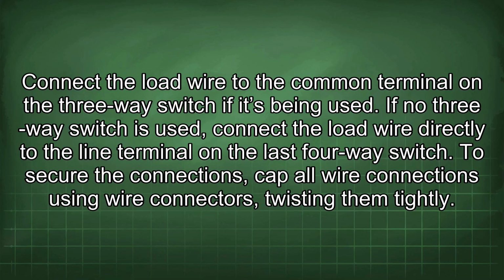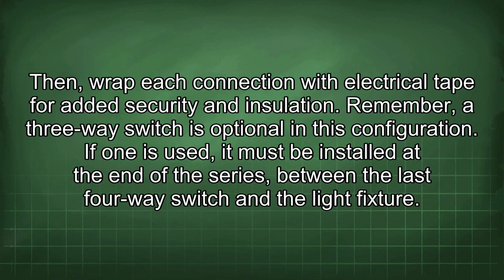To secure the connections, cap all wire connections using wire connectors, twisting them tightly. Then, wrap each connection with electrical tape for added security and insulation. Remember, a three-way switch is optional in this configuration. If one is used, it must be installed at the end of the series, between the last four-way switch and the light fixture.